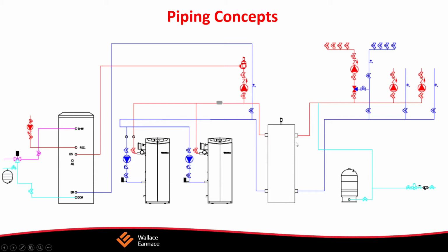Now, take a look at our near boiler piping system. Here's a simple, standard diagram for a combi boiler. Inside the boiler, we have our boiler pump. This is flowing into a primary secondary header, goes back out. We have a domestic hot water mixing valve and our domestic hot water expansion tank, and our feed is going out to the system in this direction. On the system side for the heating, we have our pumps and our zone valves, and then our returns on the other side.